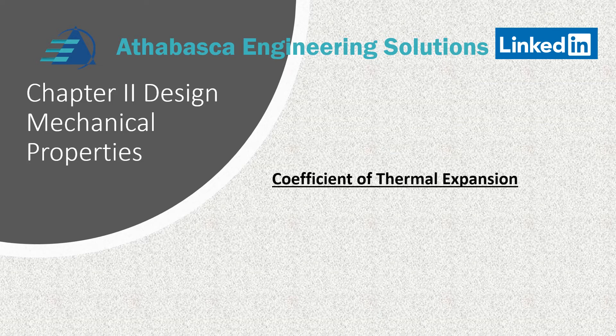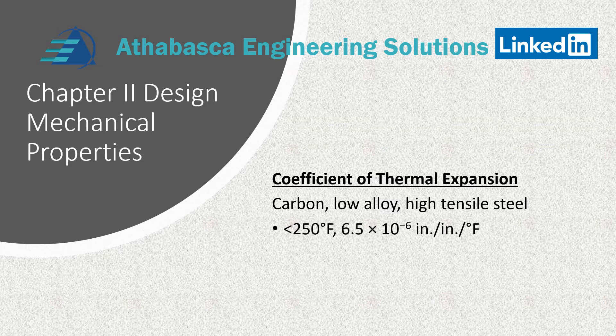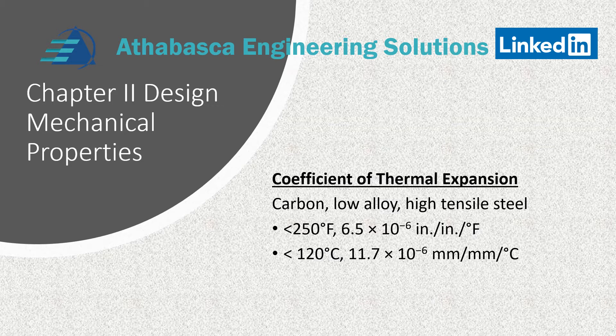Regarding the thermal expansion coefficient, they have very simplified rules. For carbon, low alloy, and high tensile steel, they give a specific value if you're below a specific temperature — in this case, 250°F or less than 120°C. Above that, it's the engineer's judgment.